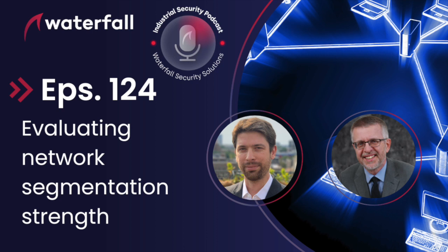The concept there is that even if you implement good cyber hygiene, even if you have good proactive defense initiatives in place, if an adversary is able to breach your environment, as part of your defense in depth you should have capabilities to monitor suspicious network traffic, alert you, and detect if an attack is going on. So NERC's drafting team is in the process of crafting a revision to the standard to include a requirement around putting sensors inside those critical networks in order to capture the traffic and detect intrusions. It's still much work in progress.